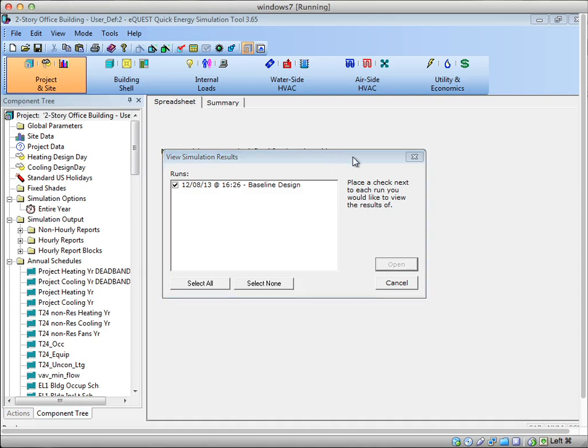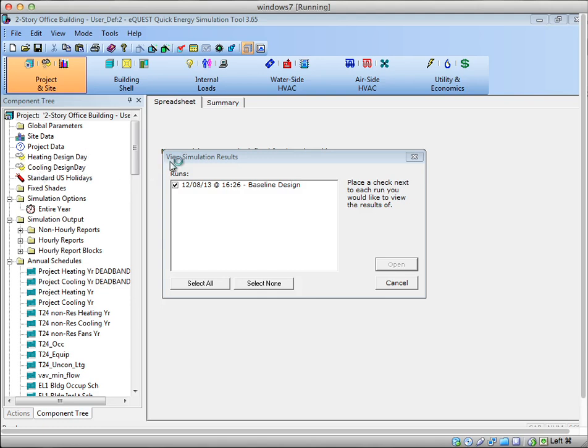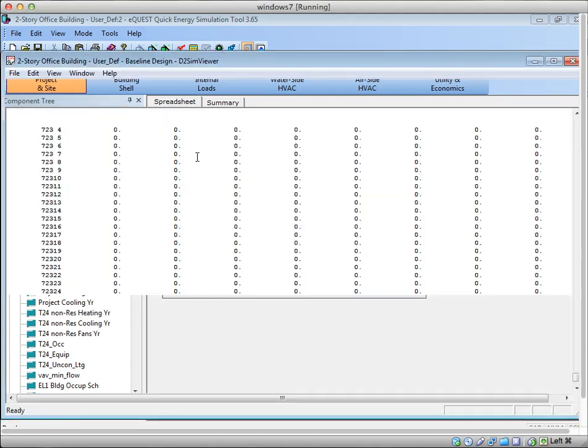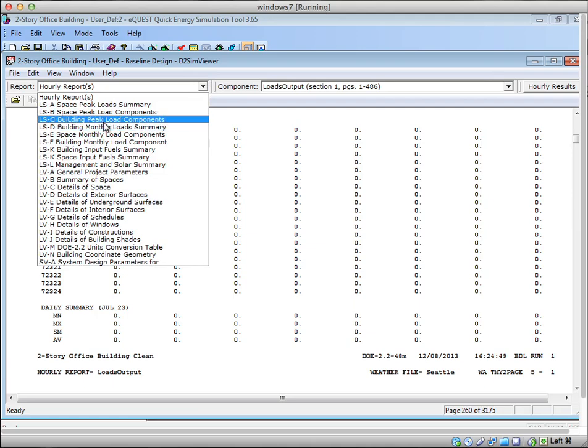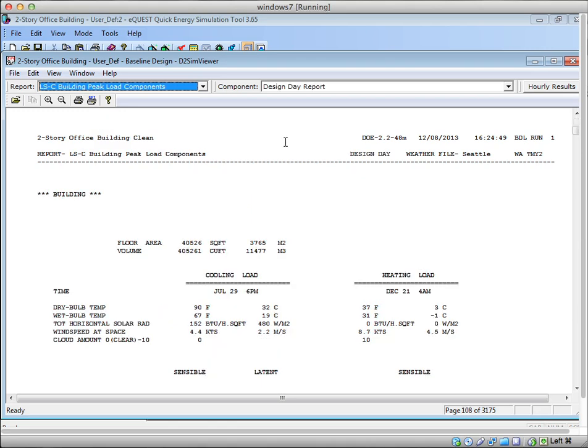You can see where this design data shows up in the sim file outputs. So if you would like to see the result of the peak load calculation, in a sense, there is a report that you can look at in the sim file that shows both the load on this cooling design day and heating design day, and then the load that eQuest found just by finding the hottest and coldest day in the weather file. So you can kind of start to see the difference. If you look at the LSC, the building peak loads components report, immediately here it comes up. It actually says at the top design day report.